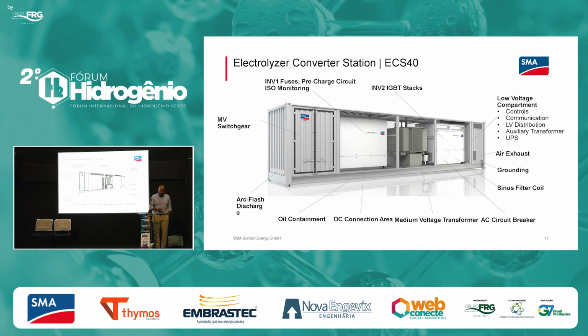If you need more power, in this case 6 megawatts, we provide a 40-foot station. The only difference is you will find 2 rectifiers in this station and a bigger transformer. We use oil-filled, oil-cooled transformers because first of all they are smaller in package size, and a 6 megawatt skid like this one is very power intense, so the transformer is oil-cooled due to efficiency and power needs.